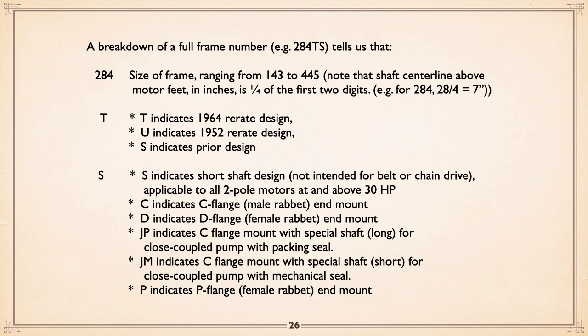Shaft center line is a little trick. You want to be real smart. If you've got a horizontal motor sitting there, the distance from the base or floor that it's sitting on to the center of the shaft will be the first two numbers divided by 4. In other words, a 284 frame motor is 28, the first two digits. If you divide that by 4, you get 7, and that'll be the distance from the base it's sitting on to the center line of the shaft, 7 inches.